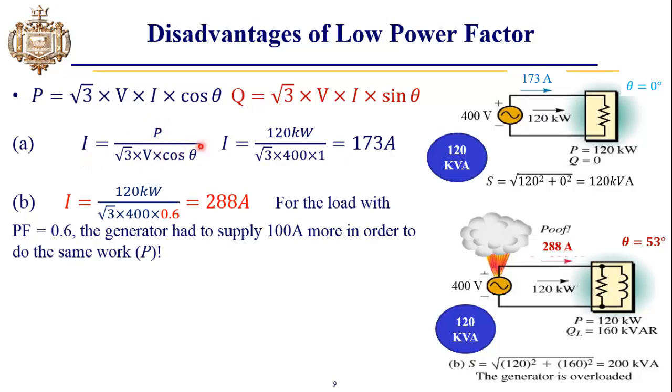For finding the current, we rearrange this formula and putting the values of all the quantities: the load power is equal to 120 kilowatts, voltage is 400, and cos θ is equal to 1. So the total current is 173 amperes, which this load is drawing from this generator. Next we have to compute the active power and the reactive power according to this formula.